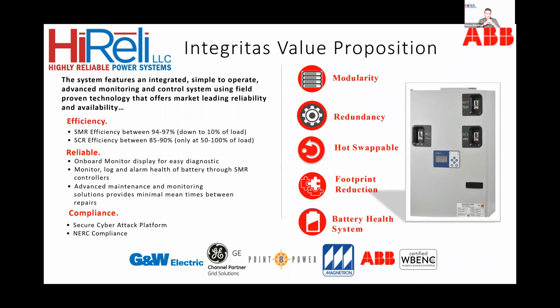Also, if you need redundant requirements, you can simply add a redundant module, giving you N+1 redundancy. Another big factor: if a module needs to be upgraded or replaced without taking the whole system down, it's hot swappable, so you can swap out the module while the system is still online. There's also the footprint reduction I mentioned, a great advantage. The battery health system is already built in, and you can do a lot of remote battery testing, which I'll talk more about in the next couple of slides.